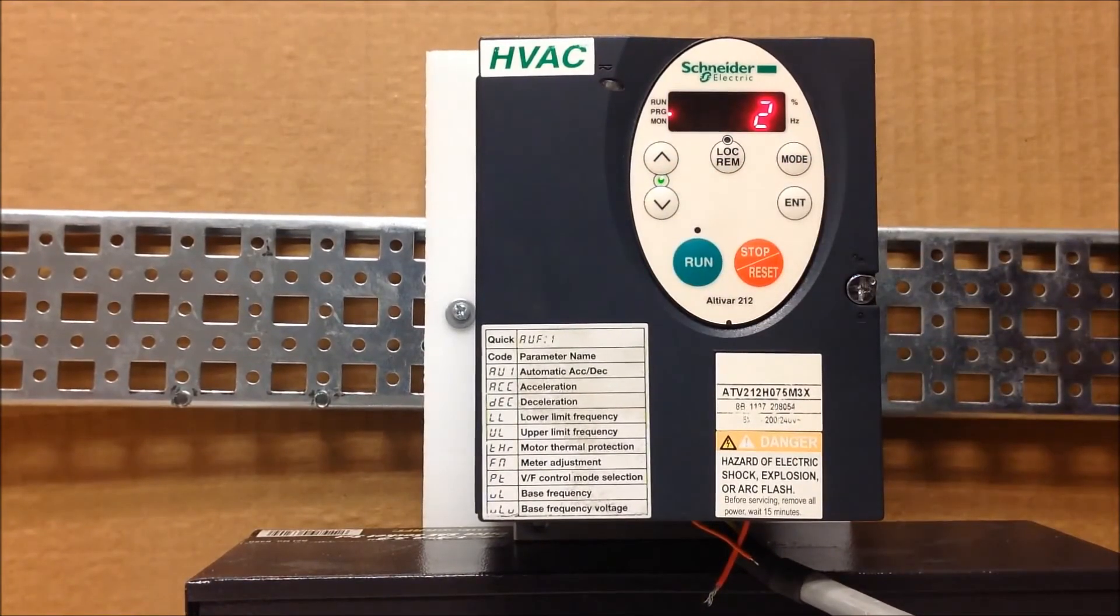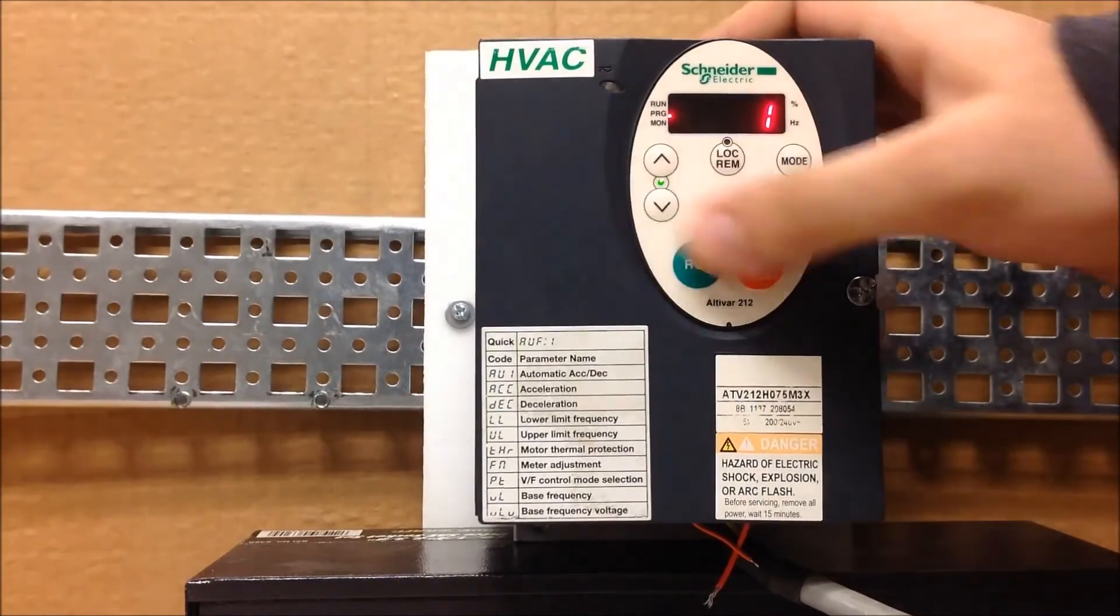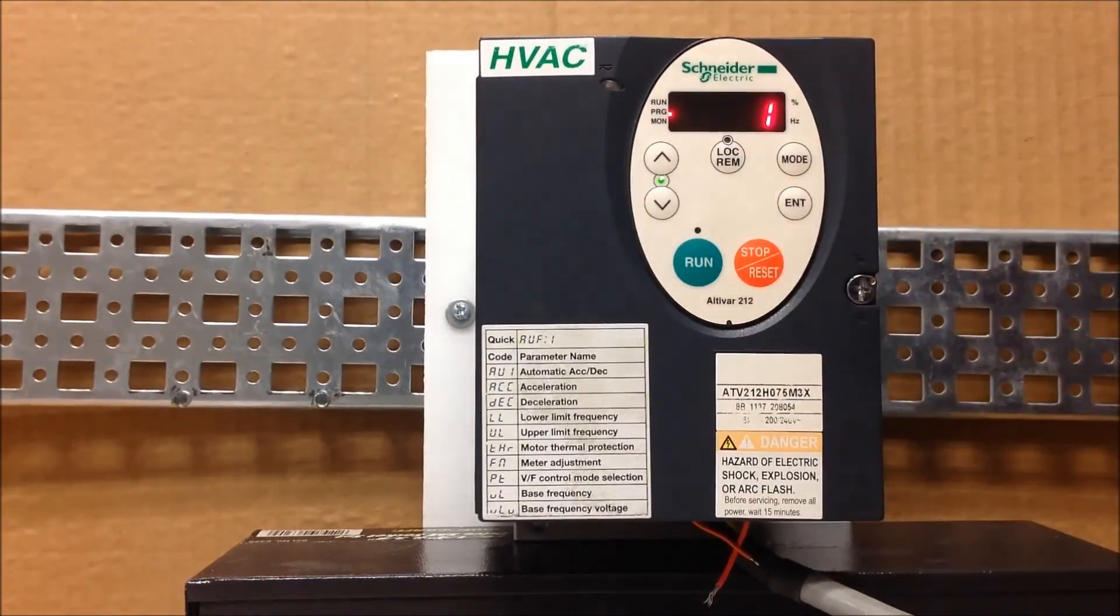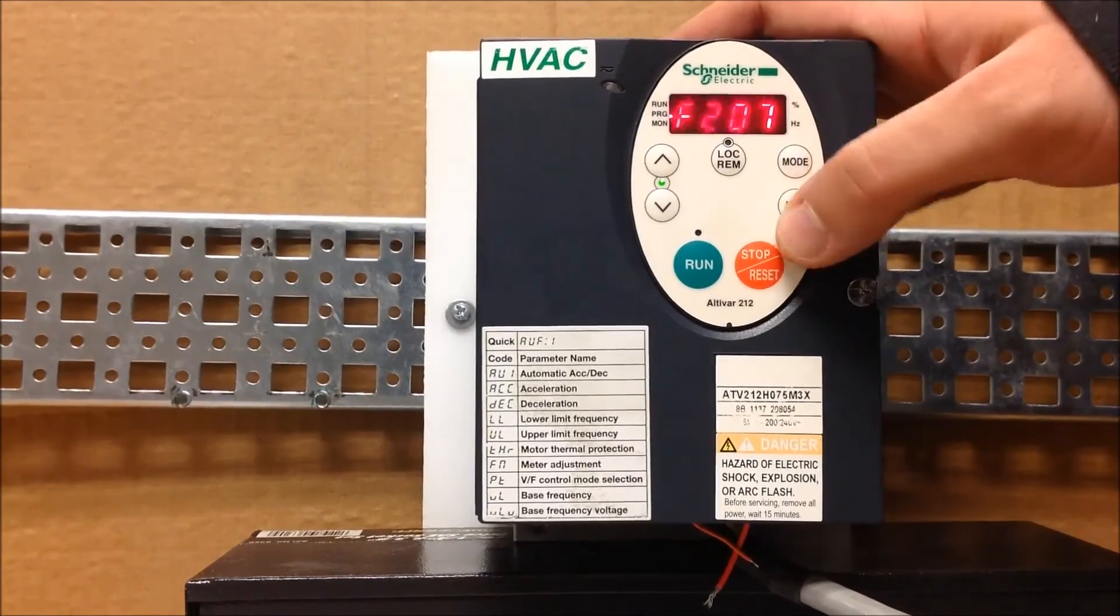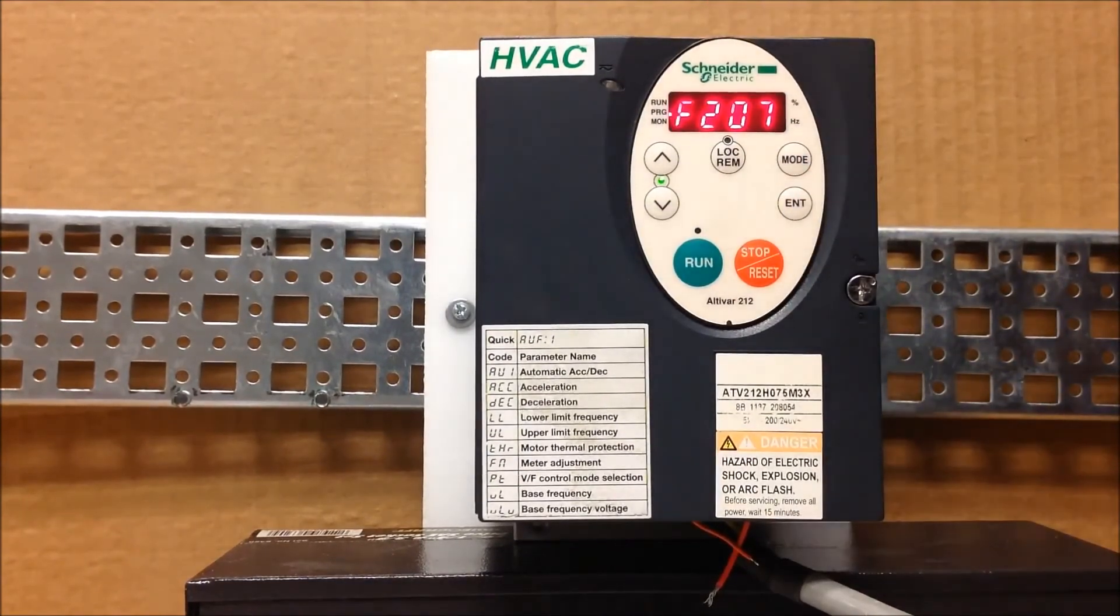You have some values you can program here, one through five just like the FMOD value. One is VIA, two is VIB, three is the keypad if you want to use that as a second source, four is communications, and five is plus or minus speed. Let's just say we're going to make it one for VIA. You're basically done programming this particular function.